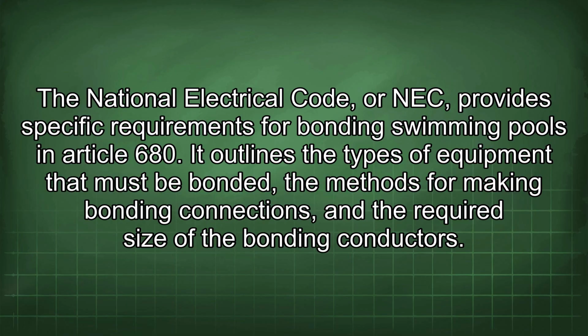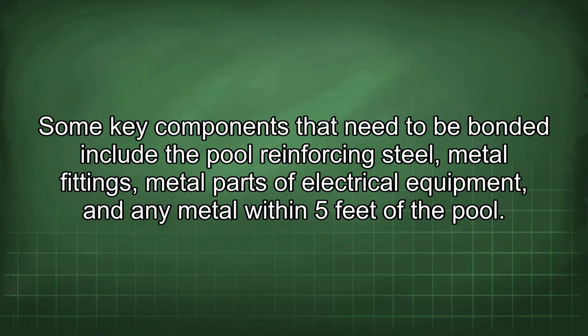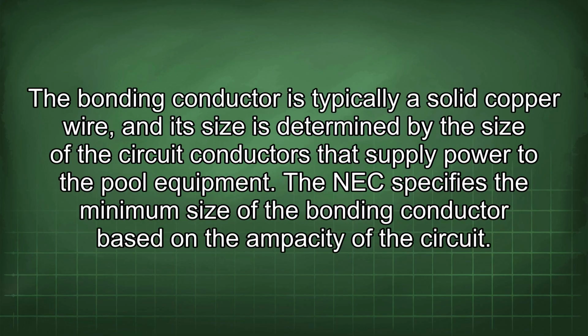Some key components that need to be bonded include the pool reinforcing steel, metal fittings, metal parts of electrical equipment, and any metal within 5 feet of the pool. The bonding conductor is typically a solid copper wire, and its size is determined by the size of the circuit conductors that supply power to the pool equipment. The NEC specifies the minimum size of the bonding conductor based on the ampacity of the circuit.